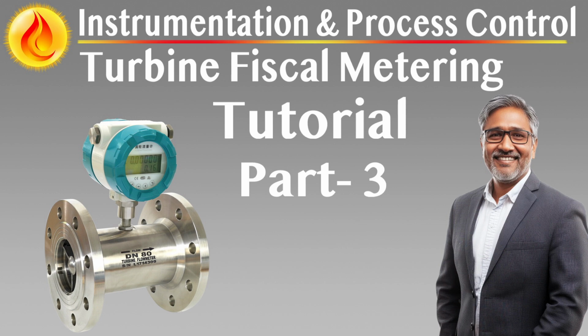Temperature measurement, high-resolution thermal sensing for volume and mass compensation. Temperature measurement in each metering run is critical for accurate volume correction and mass flow computation. All temperature sensing must be performed using electrical resistance thermometers, specifically PT100 platinum RTDs, resistance temperature detectors, with a resistance of 100 ohms at 0 degrees Celsius and an alpha coefficient of 0.00385 per degree C. These elements must meet Class A tolerance standards to ensure precision across the operating range.